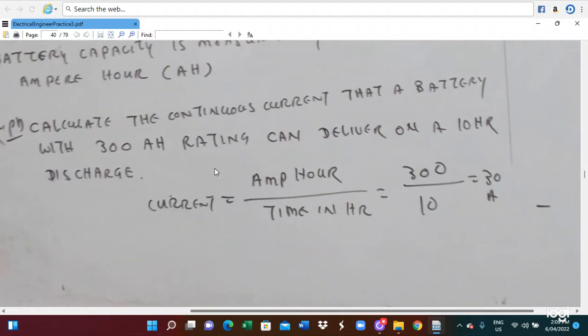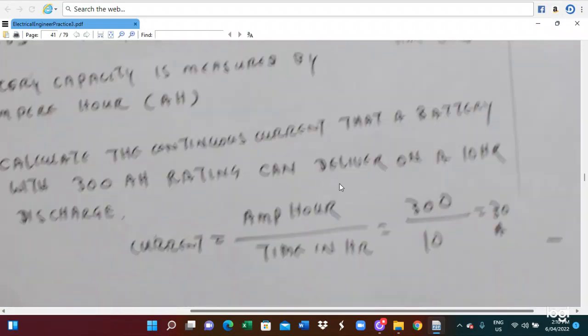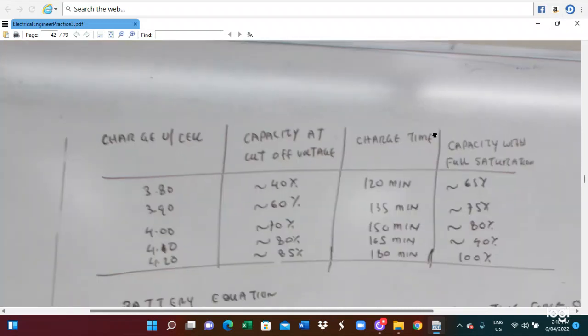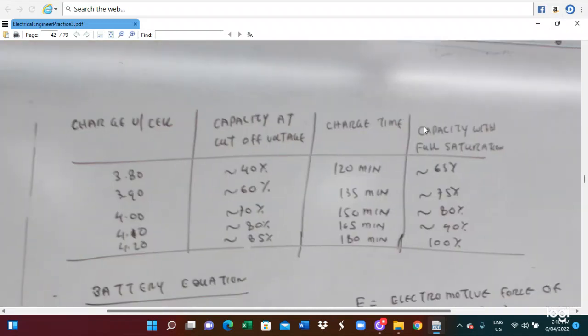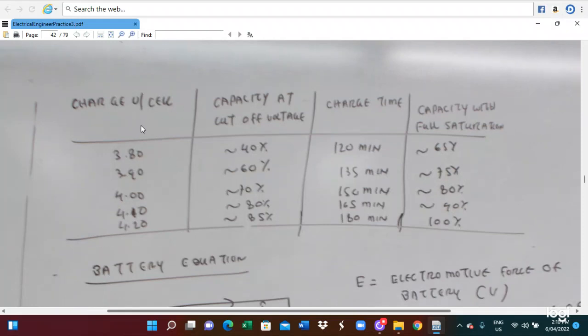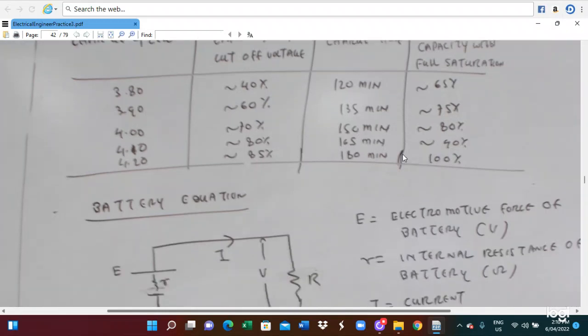So we have to calculate the continuous current that a battery with a 300 ampere hour rating can deliver on a 10-hour discharge. The current can be calculated by ampere hour divided by time in hours. So 300 divided by 10, you get 30 ampere. This is the charge volt per cell, 3.8. Capacity is the cutoff voltage and the charging curve and the capacity with full saturation. So this is the charging volt per cell and the relation diagram.